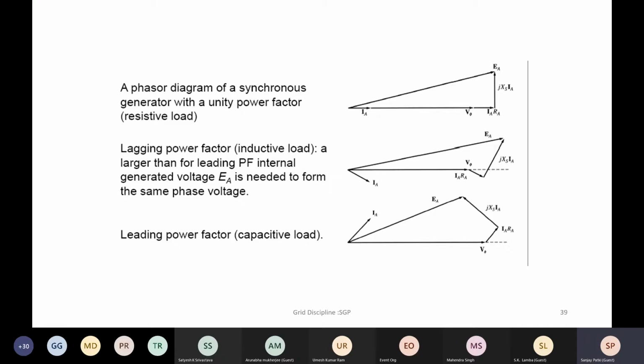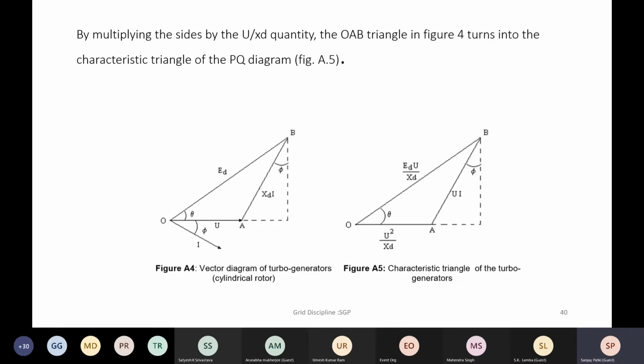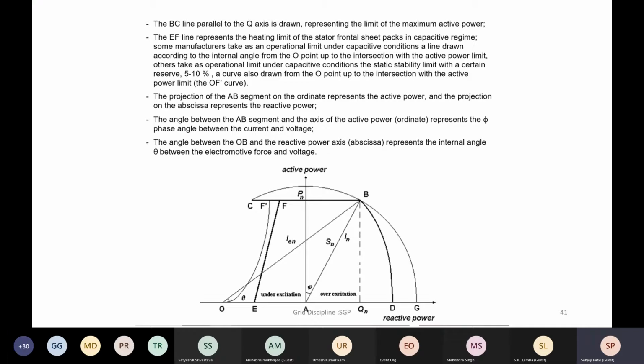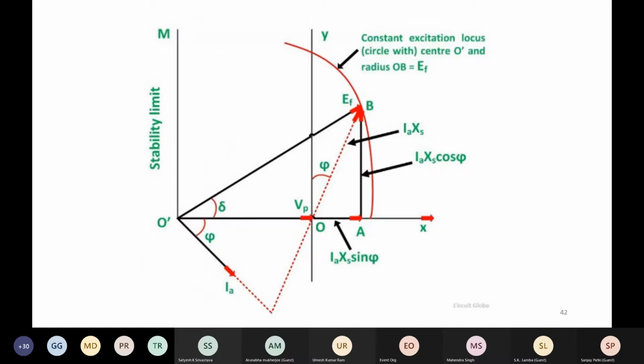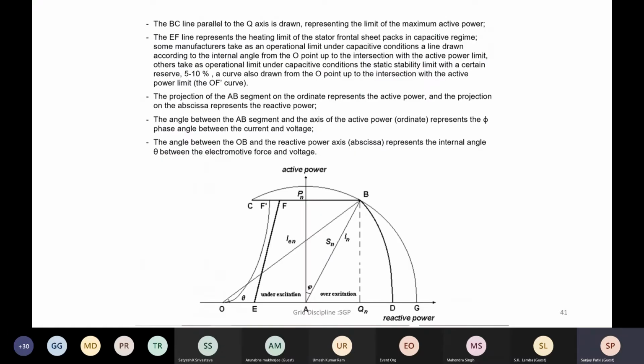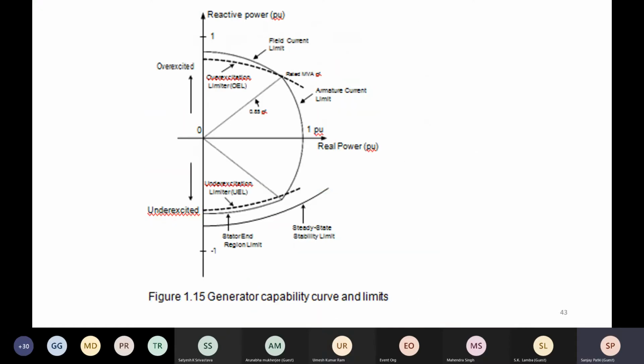The same phasor, depending on whether you are running the machine at the unity power factor, which is represented here, or the lagging power factor when you are exporting the reactive power, or the leading power factor when you are actually absorbing the reactive power, is shown here, and this further gets converted into a diagram which is called the capability curve.